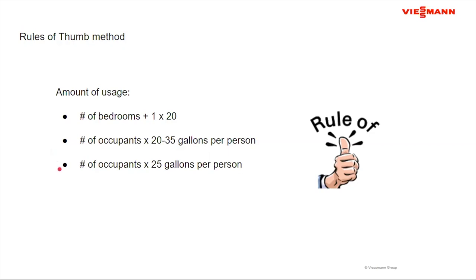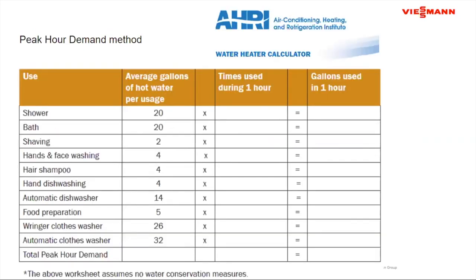Down here, number of occupants by 25, a little bit more number here. Okay. So if I look at these numbers, all three of these methodologies, I get 100, somewhere between 80 to 140, and 100 down here. So they're all pinning me somewhere about 100 gallons first hour for sizing. Again, these are rules of thumb, to kind of get into a ballpark. If I want to start to get more accurate, then I go to a methodology like this. This comes from AHRI, the Air Conditioning, Heating, and Refrigeration Institute. DOE has one as well. And I think a lot of manufacturers have these as well.